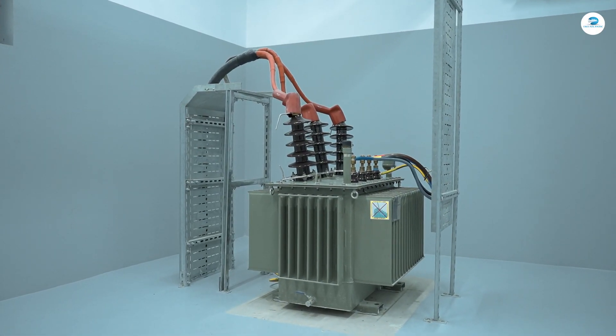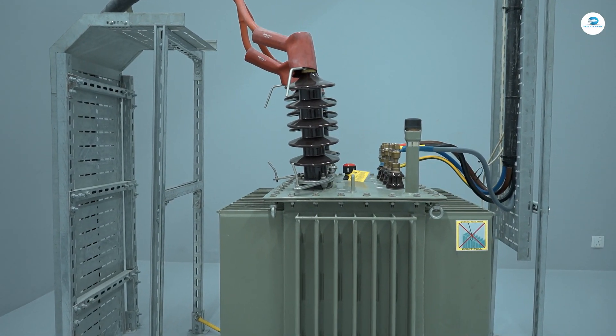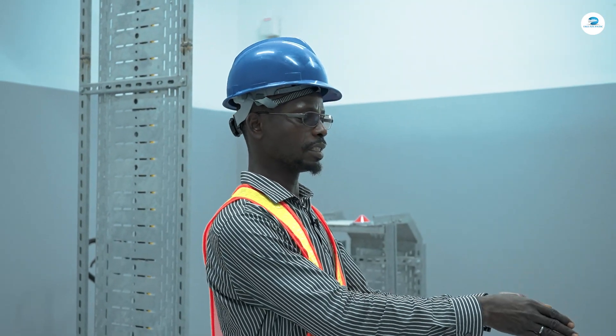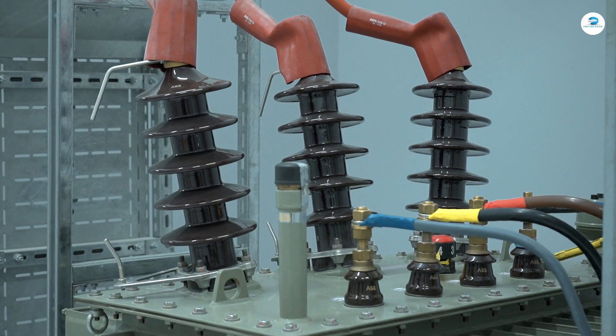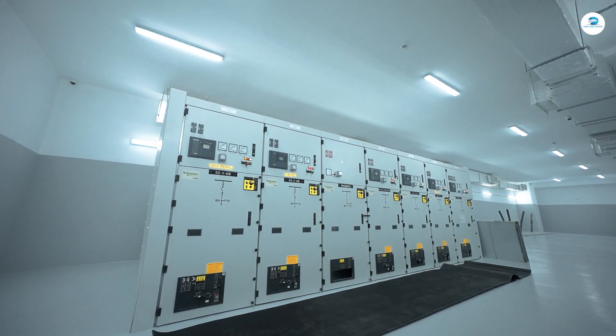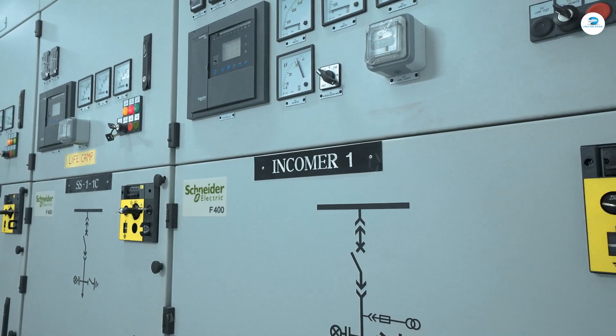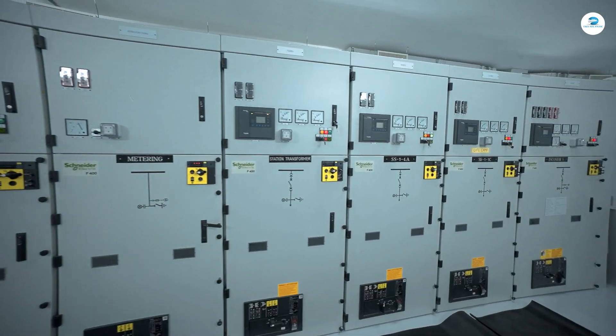This is where we have our own step-down transformer that steps down 33,000V to 400V that we use in this facility. Just as this is here, we also have this at other customers' ends — they do the same function of stepping down 33,000V to 400V. We then come up here to what we call the incoming panel. This one receives the voltage coming from the transformer. When it receives it, it sends it down along these feeders, which are called feeders because they are feeding the customers electricity.